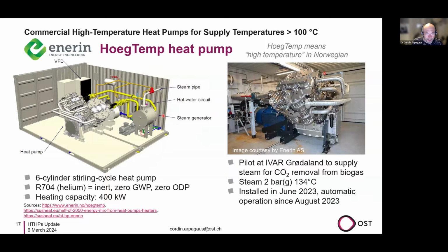Now I have some slides of particular systems. The first is from the company Enerin, a Norwegian company, a smaller company, and they have the so-called HoegTemp heat pump, a high-temperature heat pump based on a Stirling cycle with helium as refrigerant. Helium is R704, an inorganic or noble gas; the 7 comes from the refrigerant nomenclature and the 4 is the molecular weight of helium, so 704. It's inert, with zero global warming potential and no ozone depletion potential, so from the environmental point of view it's very attractive.